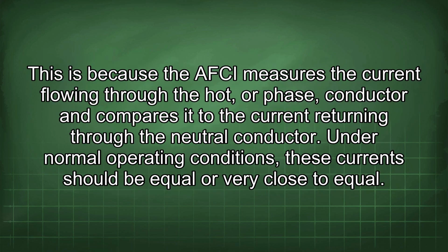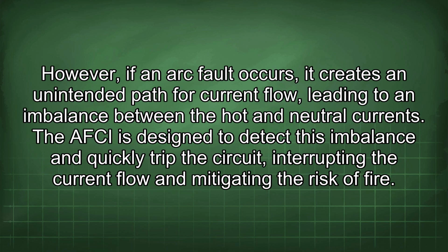This is because the AFCI measures the current flowing through the hot or phase conductor and compares it to the current returning through the neutral conductor. Under normal operating conditions, these currents should be equal or very close to equal. However, if an arc fault occurs, it creates an unintended path for current flow, leading to an imbalance between the hot and neutral currents. The AFCI is designed to detect this imbalance and quickly trip the circuit, interrupting the current flow and mitigating the risk of fire.